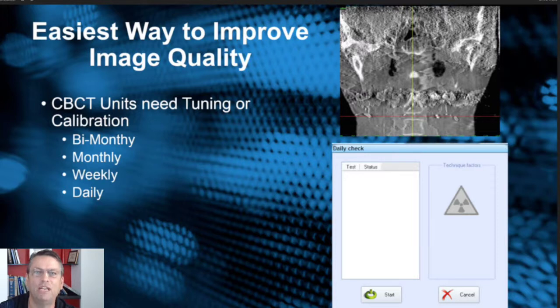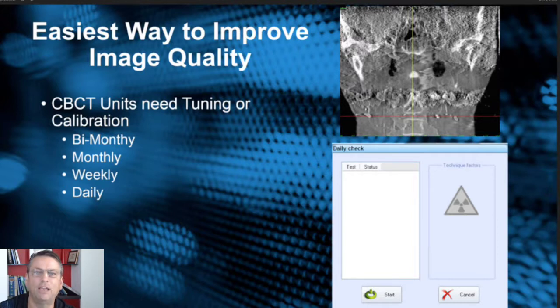Cone beam CT units need tuning or calibration routinely. You should look into your manuals and see whether or not your machine requires bi-monthly, monthly, weekly, or even daily calibrations. We have several different machines from different manufacturers and some require a daily calibration while others have longer periods, but it really is a great way to help improve your image quality without having to do much work.